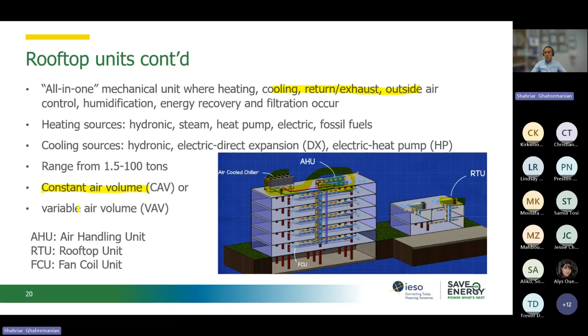And again, they come in different sizes, and they can work under a constant air volume system, or they can provide a variable air volume system actually. So in this slide, we have a constant air volume system, which provides a constant CFM of airflow to the area. So basically, the return air is coming from here, the outdoor air is coming here, and then the air gets filtered, and then it goes to the supply fan, and then we have the coil, which is doing the heat pump role for us, and brings the air that we want, either cold air during the summer season or warm air during the winter season actually.